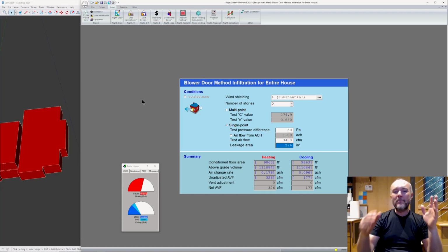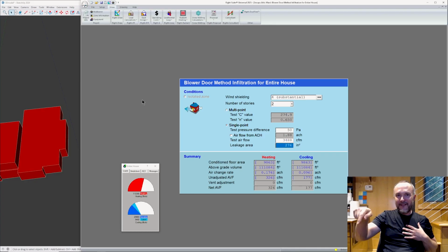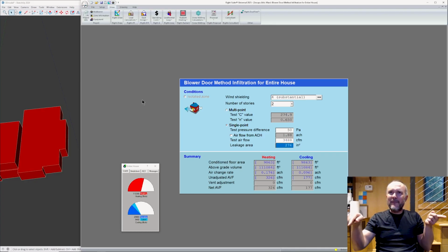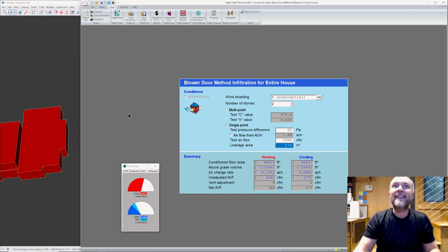because if somebody said, what's your blower door target? And they're like 1 ACH 50, and then the HVAC designer's like, okay, 1, I'm going to put that in here. And what the builder meant was based on the real volume, and what the HVAC designer meant was based on the other, that we could be off by a factor of 2. That's majorly problematic. So just know that that is something that we need to be talking about. They're trying to fix it again, but I don't, can anybody fix everything in the world?